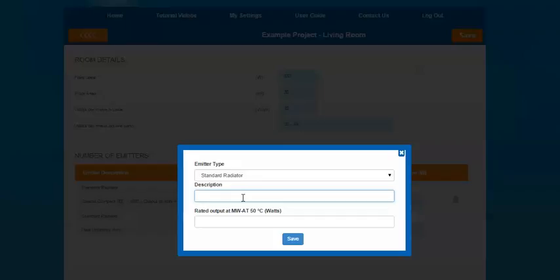The description is predominantly the manufacturer's name, model and dimensions of the radiator you're installing. You then need to add the rated output at mean water air temperature 50 degrees, based on the manufacturer's guidance. A lot of manufacturers advertise their products at a mean water air temperature of 50 degrees, so it should be fairly easy information to get hold of, but you would need to contact your manufacturer for this.